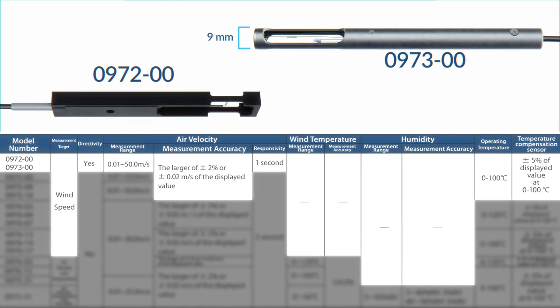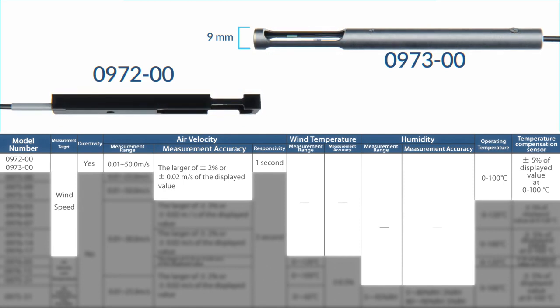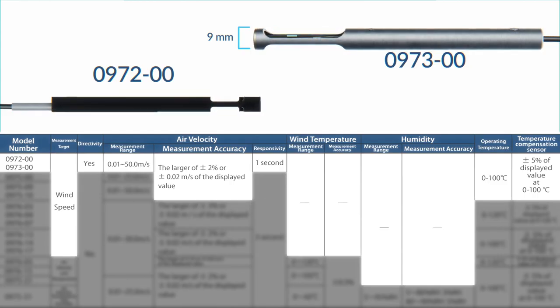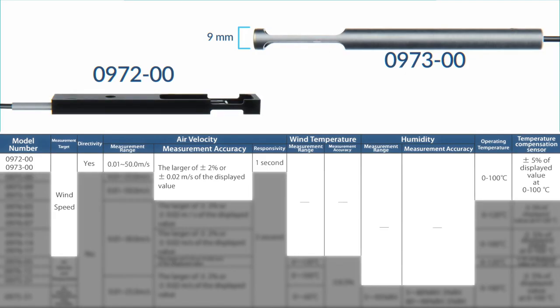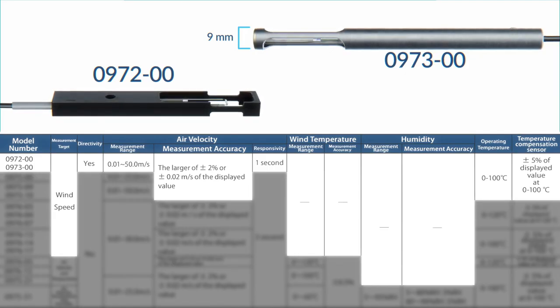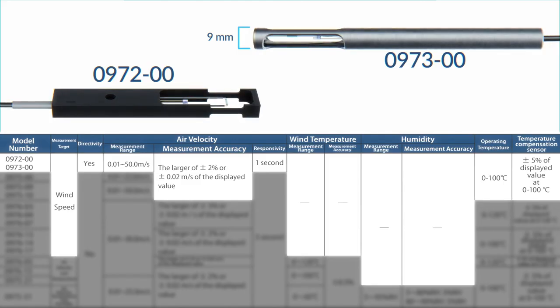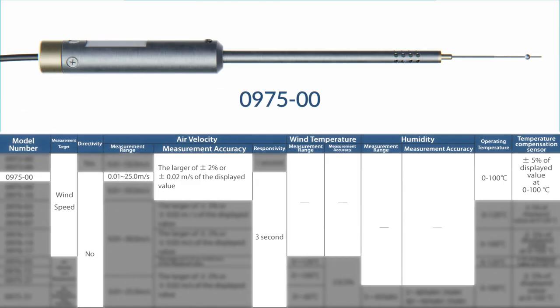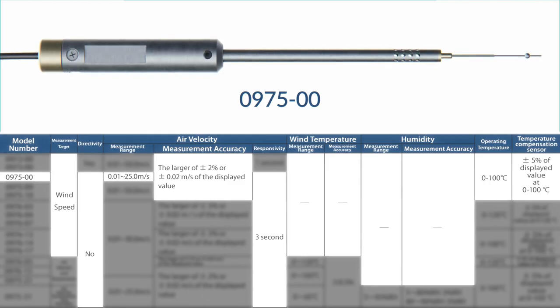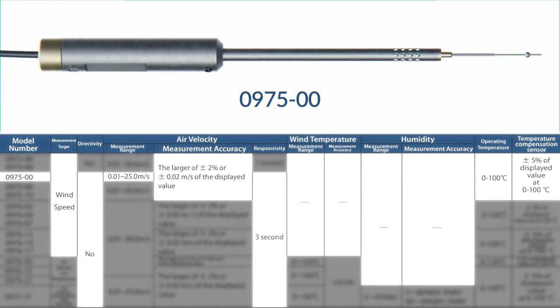What separates them from one another is their form factor. 0972-00 has a flat profile for easy mounting using a fixture, and 0973-00 has a cylindrical form with a diameter of 9 millimeters for holding the probe by hand or inserting the probe through a round hole. Model 0975-00 is an omnidirectional probe that measures air velocity within a range of 0.01 to 25.0 meters per second. It's accurate to the larger of plus minus 2% or plus minus 0.02 meters per second of the displayed value, processed every 3 seconds, and operates at temperatures from 0 to 100 degrees Celsius.